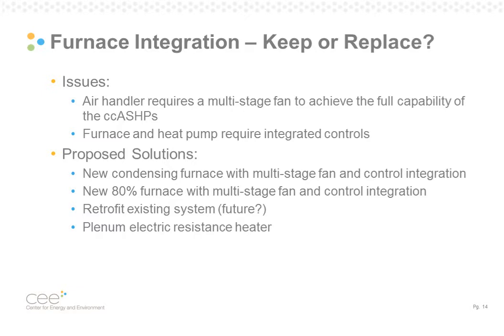The original intent of this project was to integrate the air source heat pump with the homeowner's existing furnace. However, we quickly found out that this is not something that installers or manufacturers would do. The 2 issues that they cited were, one, that the air handler needs to have a multi-stage fan in order to achieve the full capability of the cold climate air source heat pumps. And 2, that the furnace and the heat pump require integrated controls.